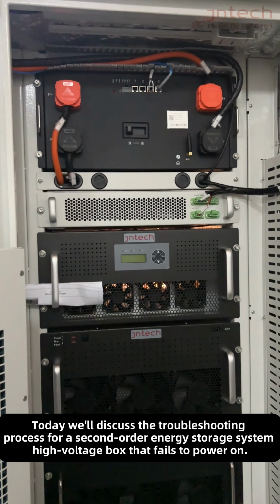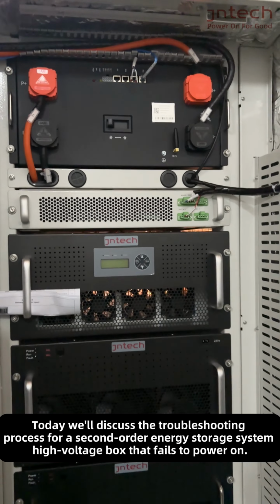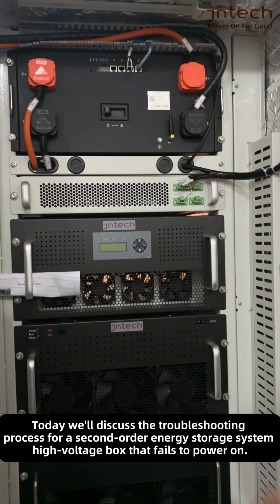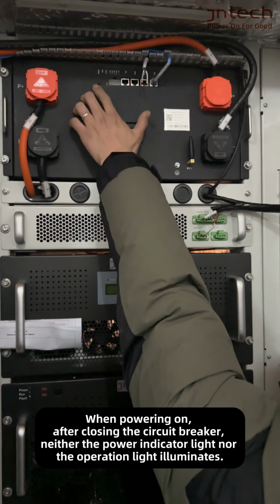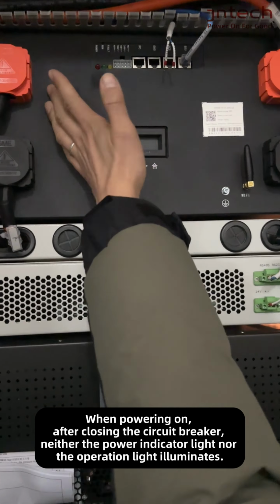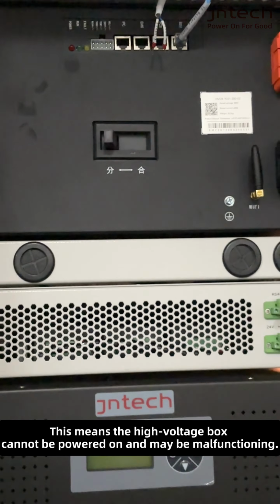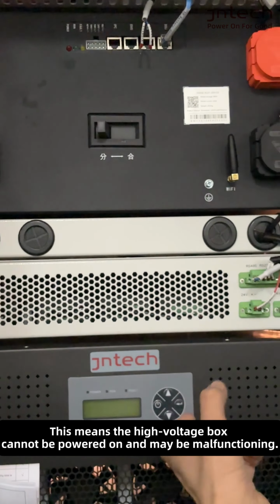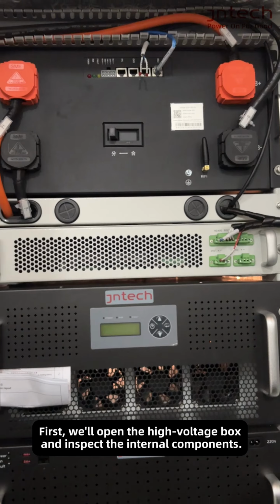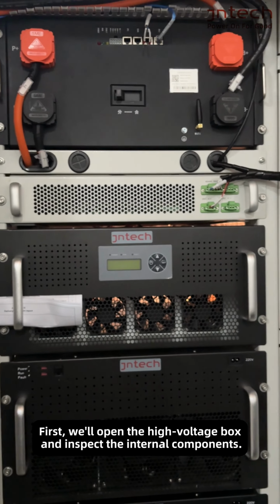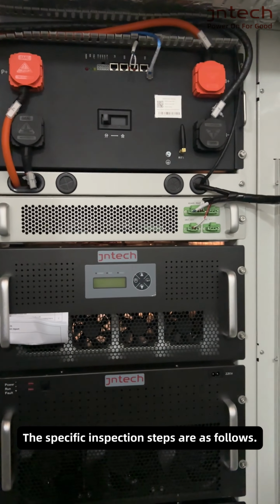Today we'll discuss the troubleshooting process for a second-order energy storage system high voltage box that fails to power on. When powering on, after closing the circuit breaker, neither the power indicator light nor the operation light illuminates. This means the high voltage box cannot be powered on and may be malfunctioning. First, we'll open the high voltage box and inspect the internal components. The specific inspection steps are as follows.